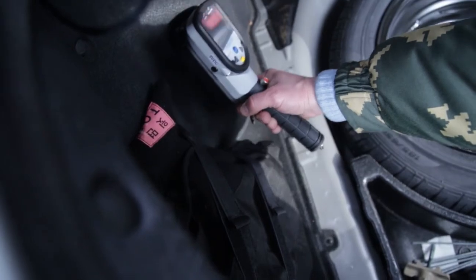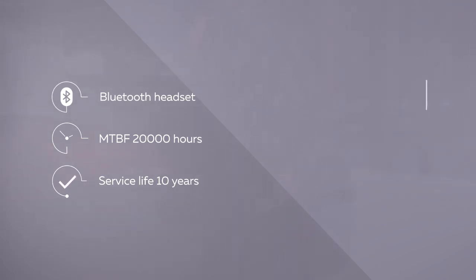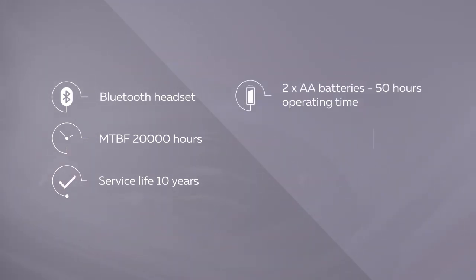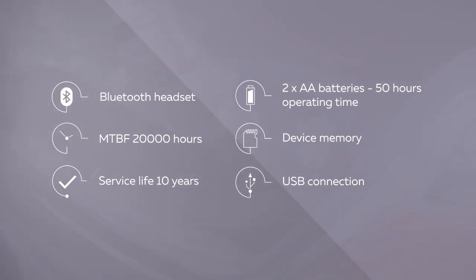PM2030 is convenient and easy to operate. You can also use a Bluetooth headset to monitor the sound frequency rate in the surroundings with excessive noise level. The device features a long lifetime. Mean time between failures is at least 20,000 hours, and average service life without changing the radiation source is at least 10 years. The operating time for 2 batteries is 50 hours, and the measurement data are saved in the device memory and can be used to build the library of the scanned items. To transfer the necessary data to your PC, use USB connection.